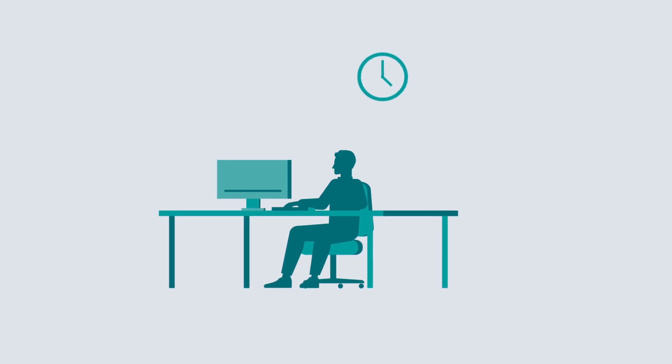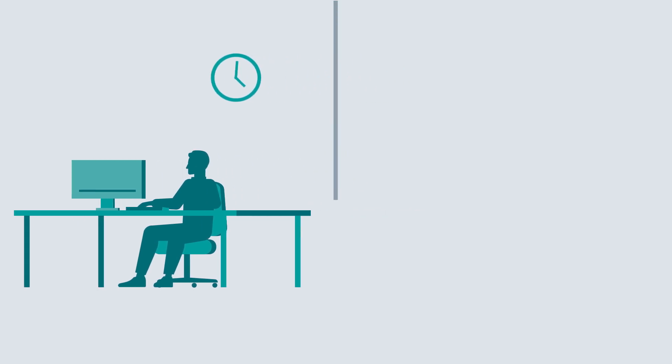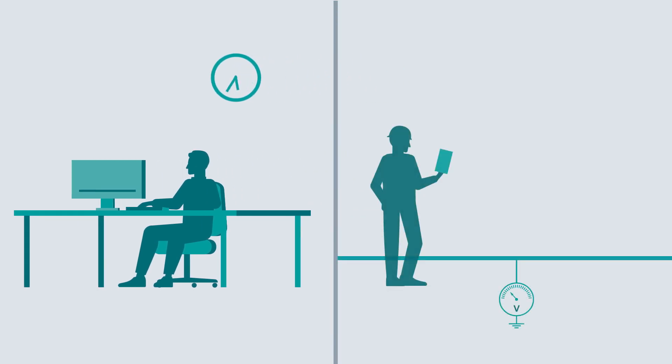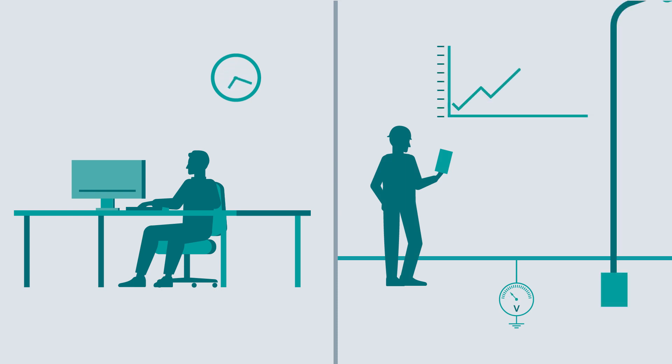A colleague measures the rail potential opposite to the earth potential. Based on the results, he identifies unintentional changes which indicate stray current concentration by insulation faults.